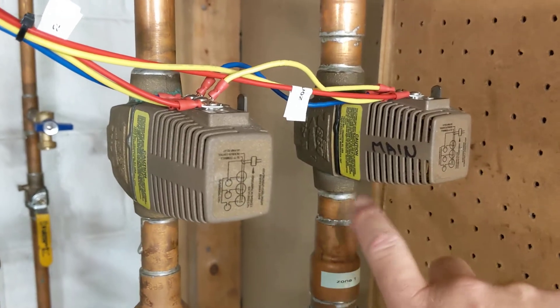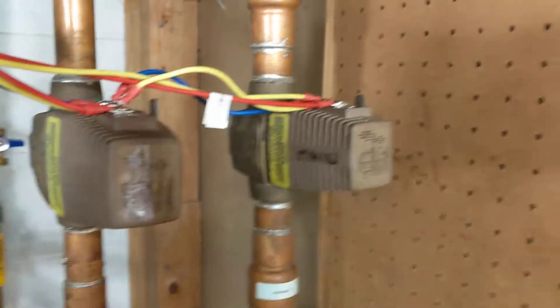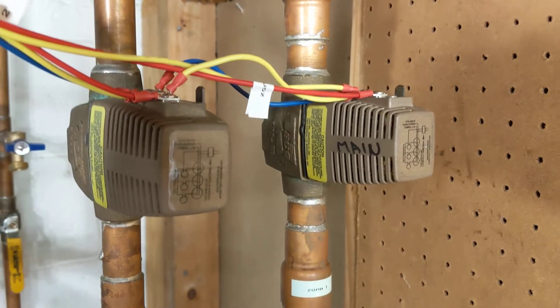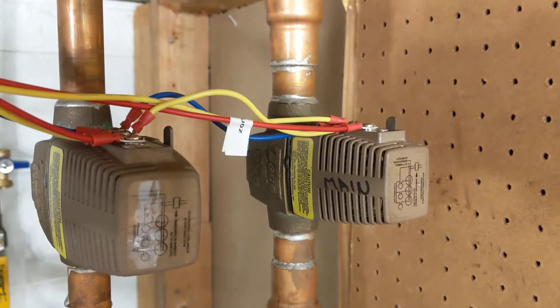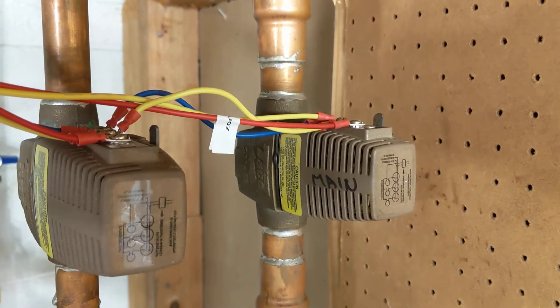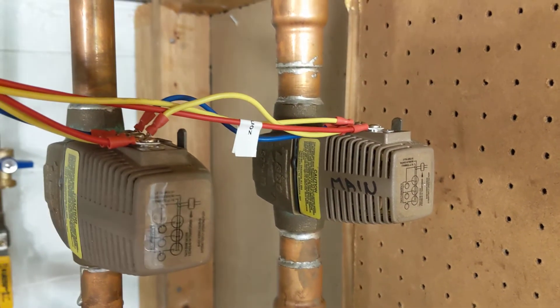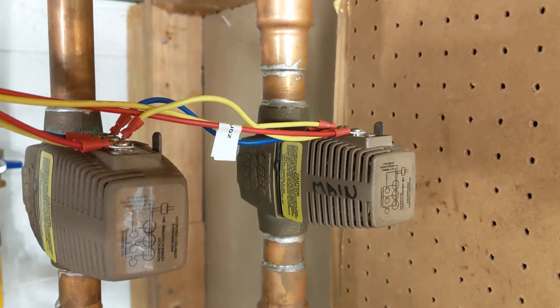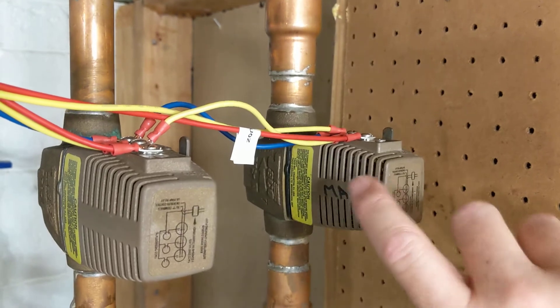These Taco zone valves control the flow of hot water, but they do more than that — they also control the boiler itself. So when you set your thermostat to call for heat, whether it's a mercury switch where you turn it to call for 75 degrees, or an electronic thermostat where you tap heat up, the thermostat closes the switch in your living space and sends power to this Taco zone valve.